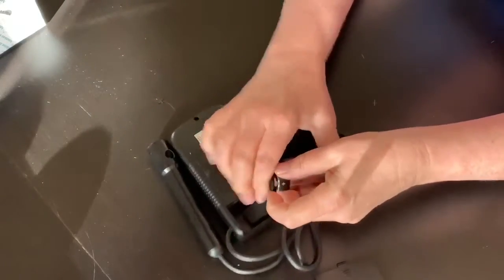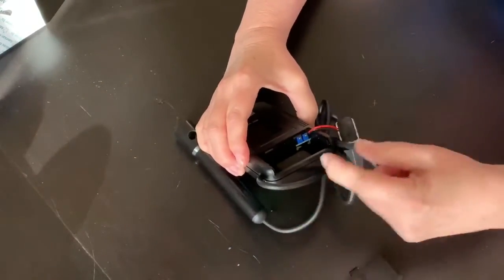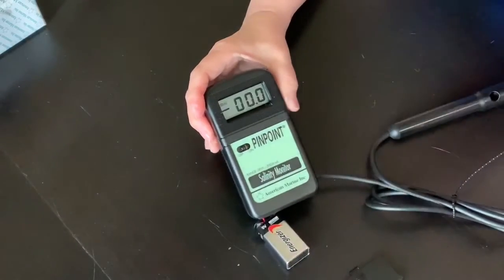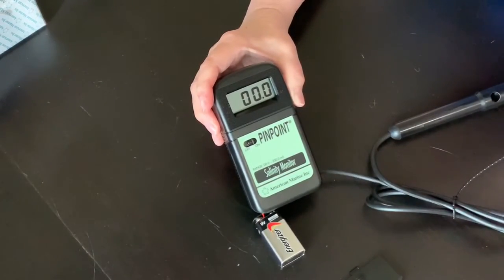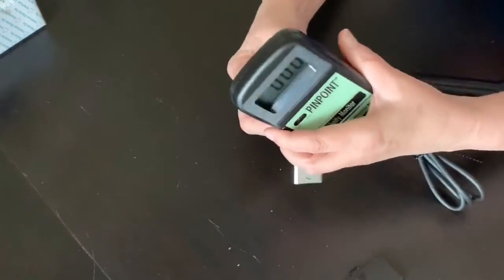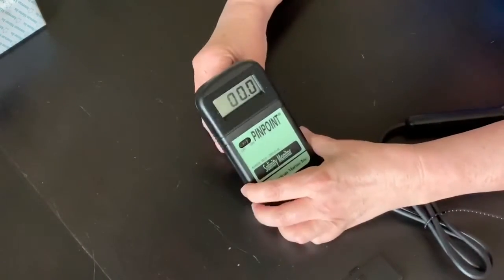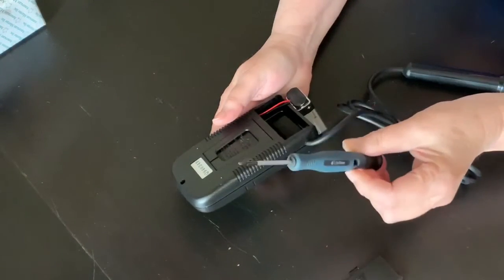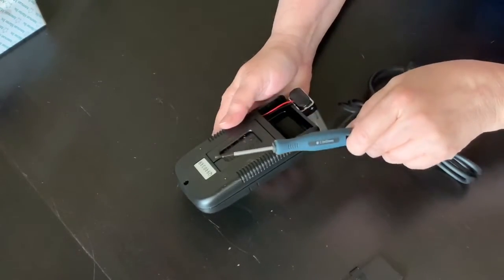I'm not going to put the battery in place yet because I need to do the calibration. Calibration involves using one of the two tiny screws located inside the battery compartment. Let's start by powering it on — it all looks good. On the back is a little pop-up stand, which is handy once assembled to set it on a table and observe the readings. I have a tiny screwdriver that I use to calibrate my pH monitor, and I'm going to try it for this one — it is the right size.